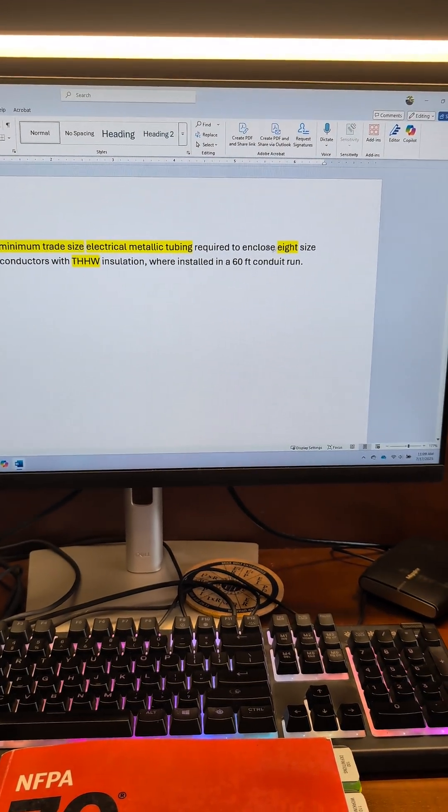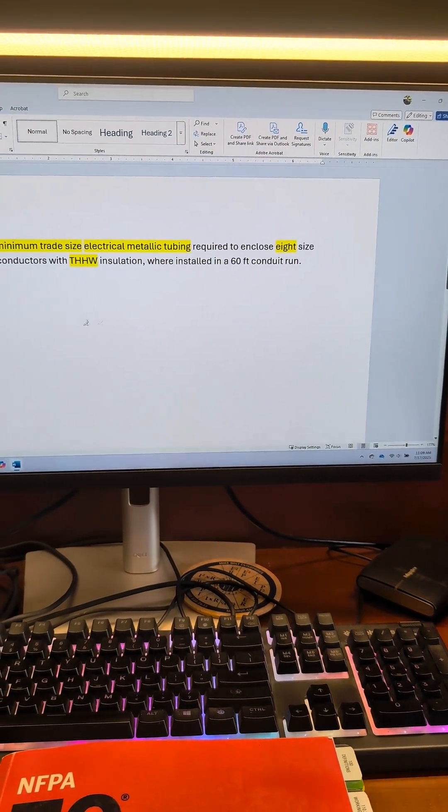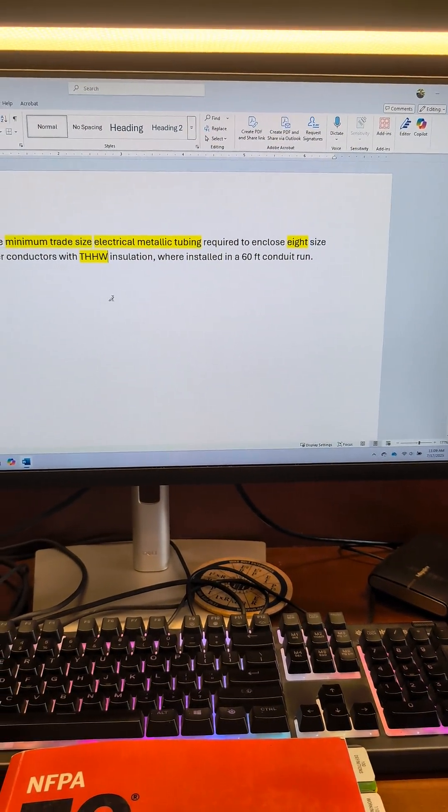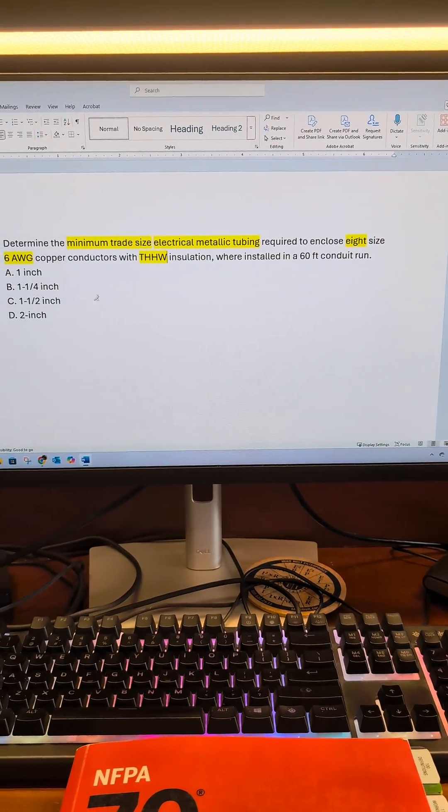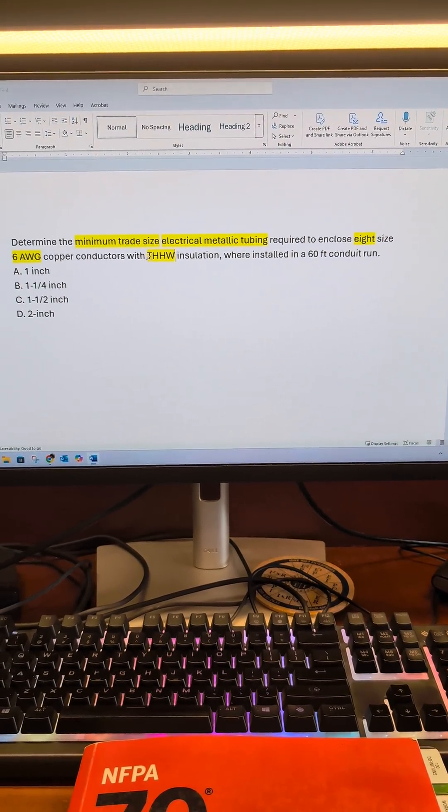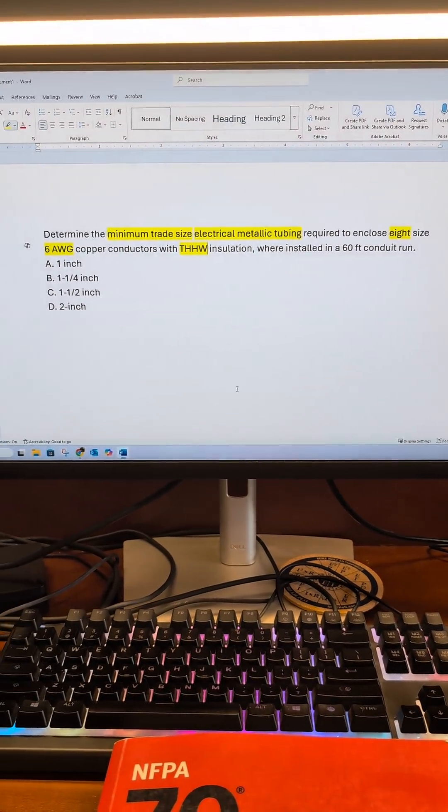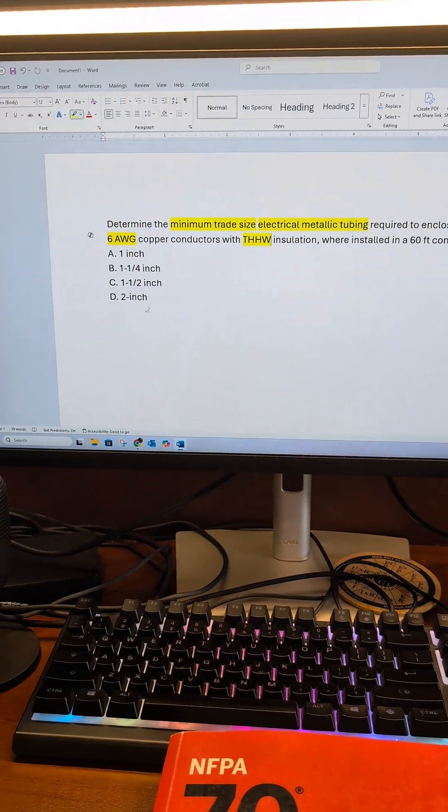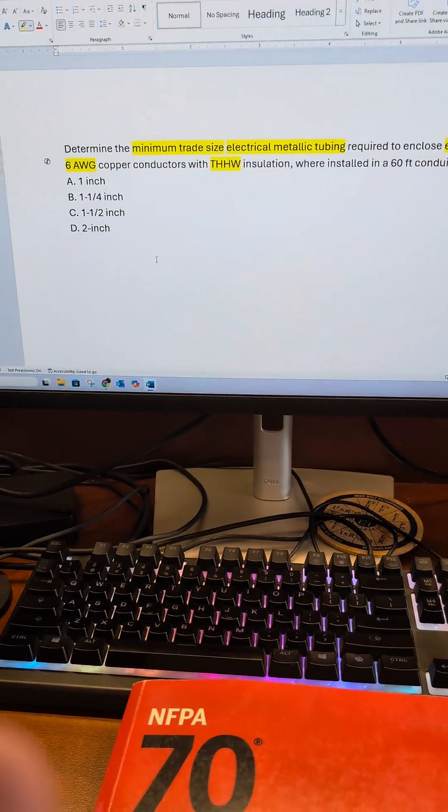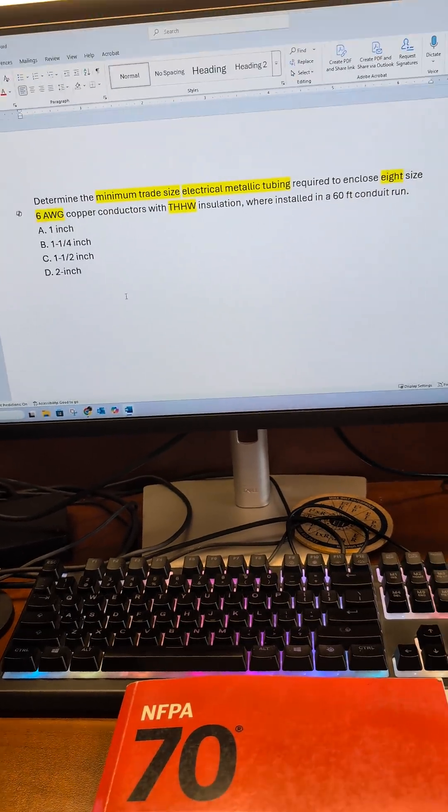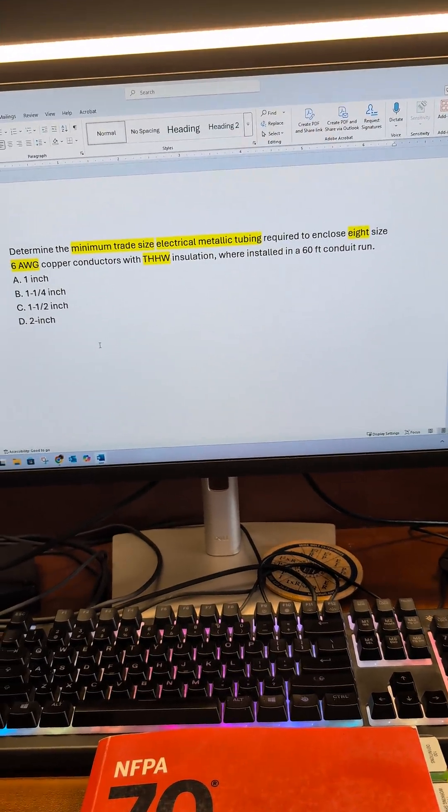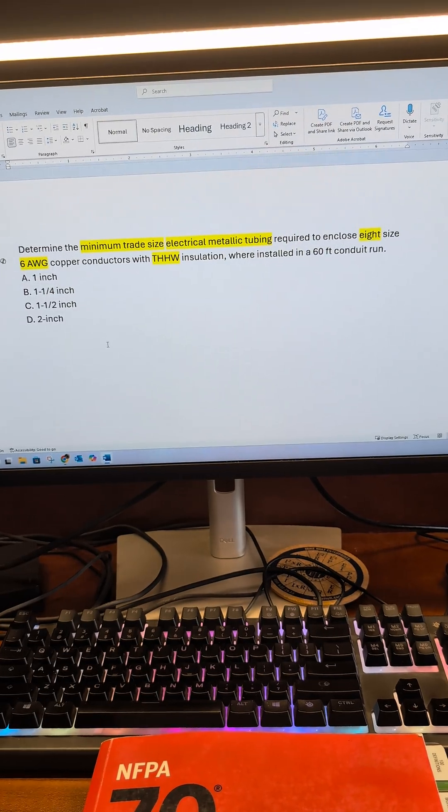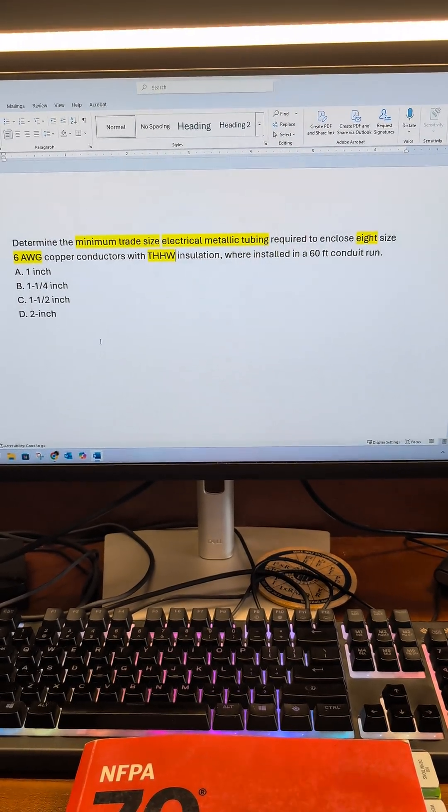This 60-foot conduit run is just fluff and extra information. You don't size your EMT based on the length of run. You base it on the volume. So we'll do it the quick and easy way, and then I'll make a supplement video on how to do this the mathematical way.